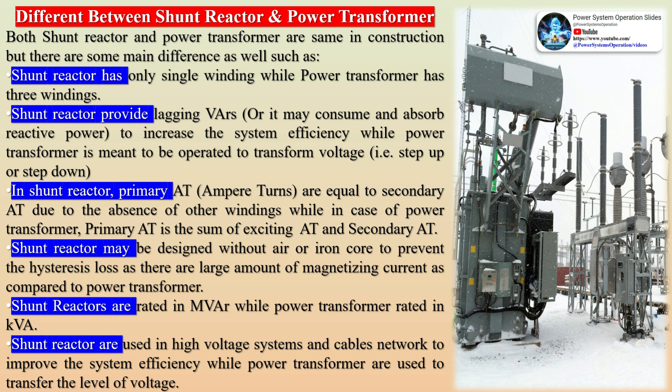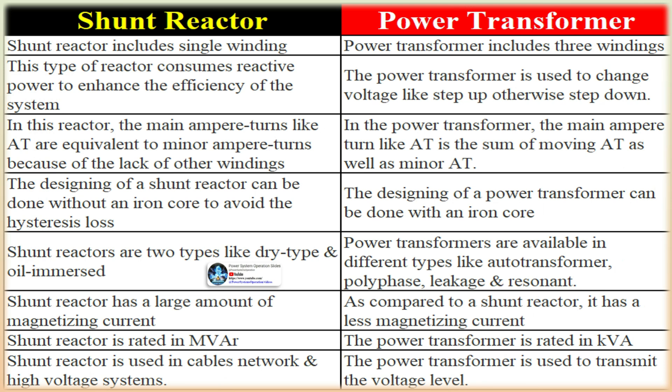A shunt reactor has only a single winding while a power transformer has three windings. Shunt reactors provide lagging VARs, consuming and absorbing reactive power to increase system efficiency, while power transformers are meant to transform voltage (i.e., step up or step down). In a shunt reactor, primary ampere-turns equal secondary ampere-turns due to the absence of other windings.